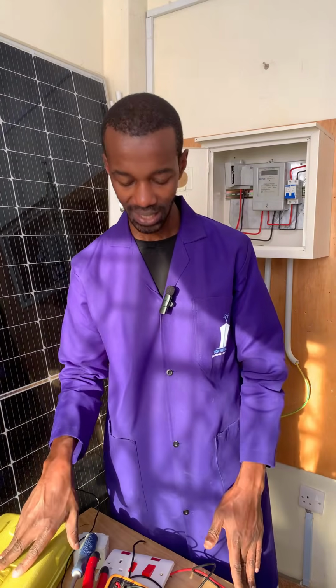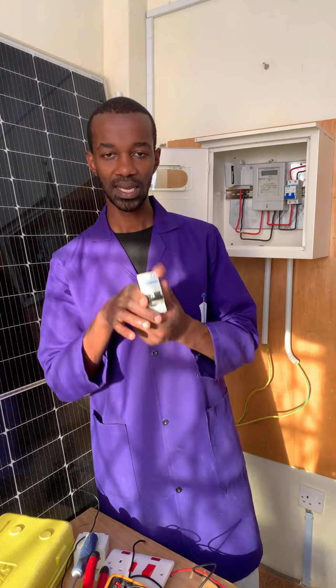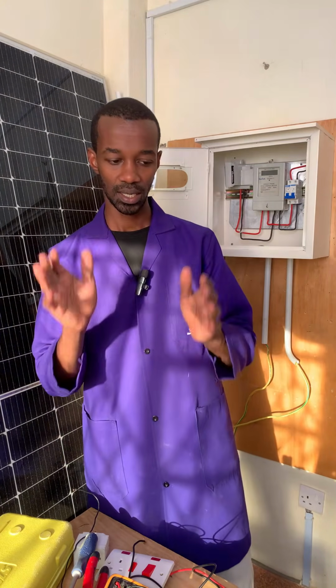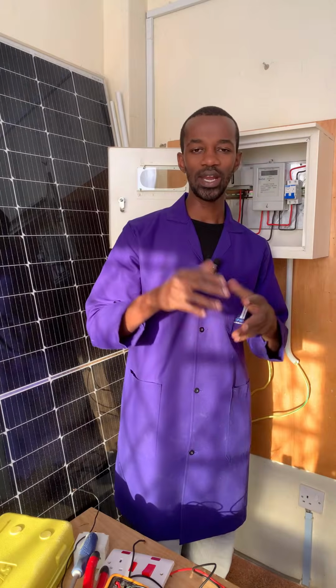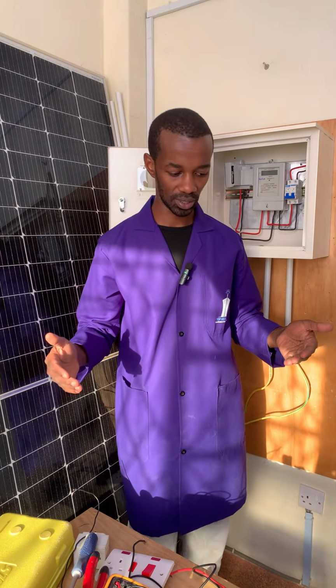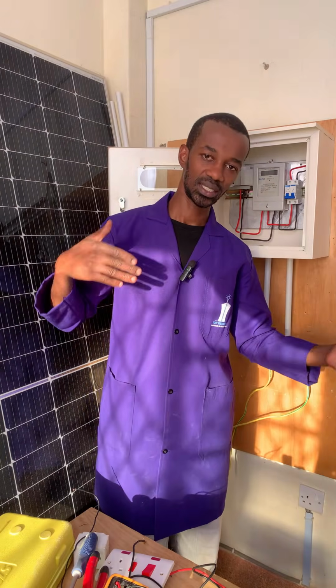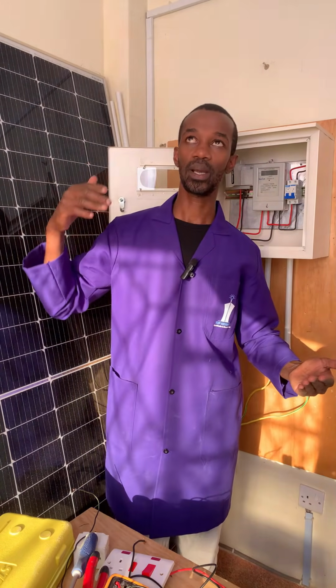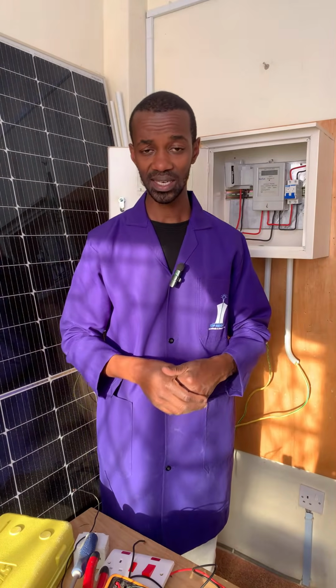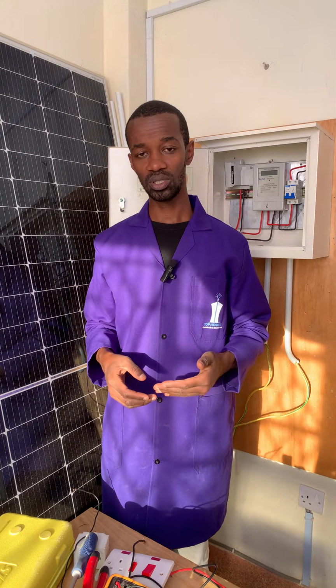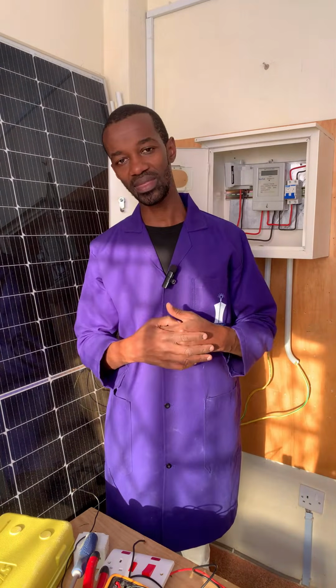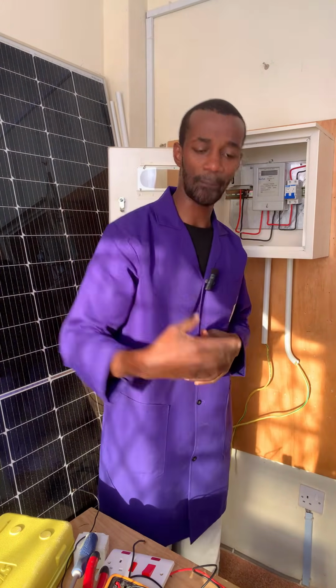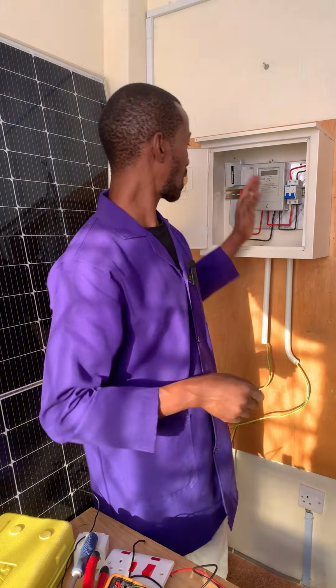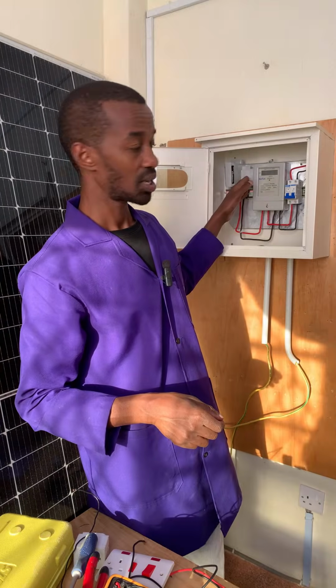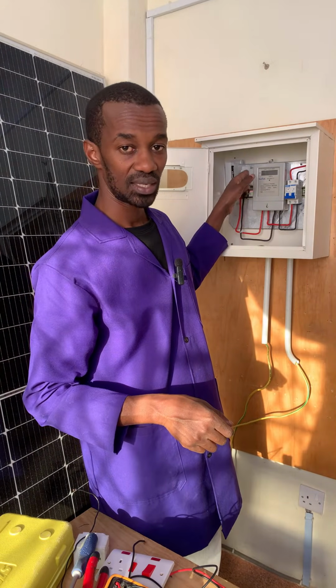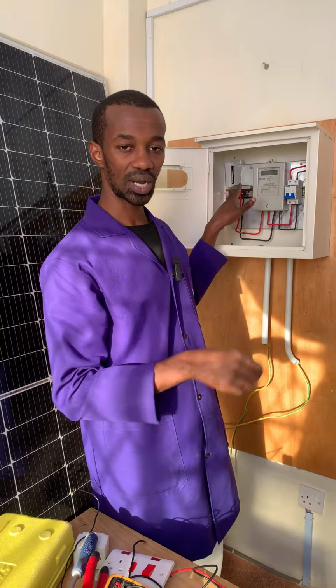So once we test for that, now you can switch on that DPMCB, and then test for the voltage again. Connect the loads progressively. What do I mean progressively? Connect the sockets, connect the fridge, ensure that everything is running properly, switch on the lights, and then switch off the heavy loads, switch them on back again, and see whether there is a problem. Sometimes it can even persist. The customer may think that you are lying. So you can also go further and check the meter box. Check the meter box. If there is an issue here, you can repeat the same.